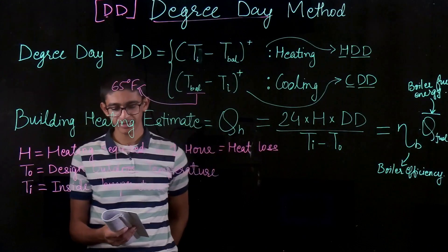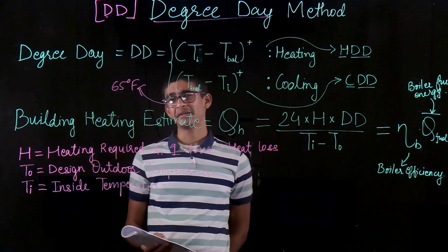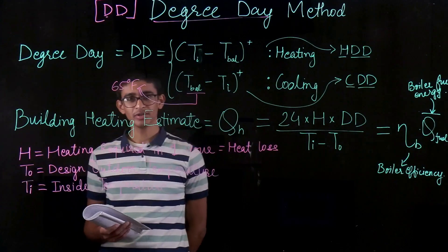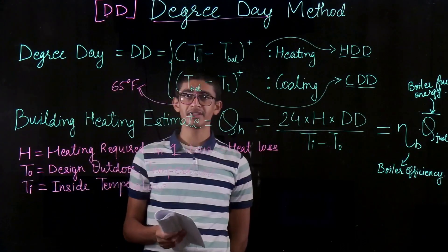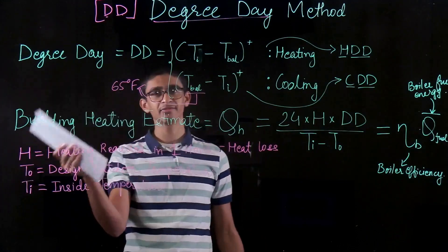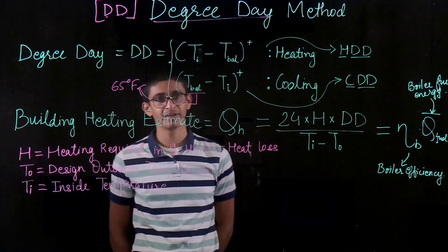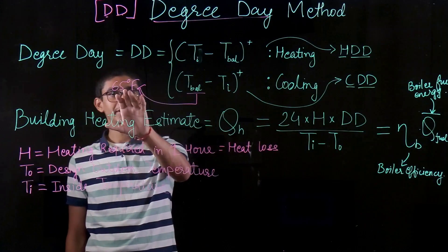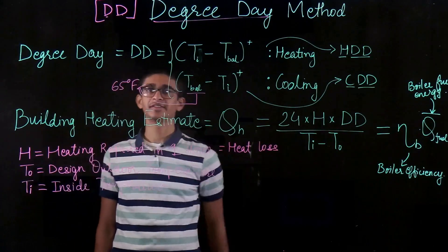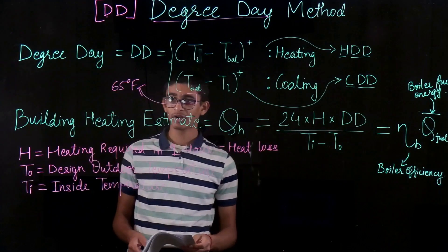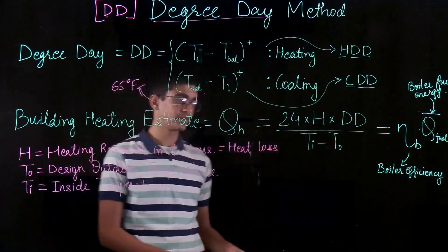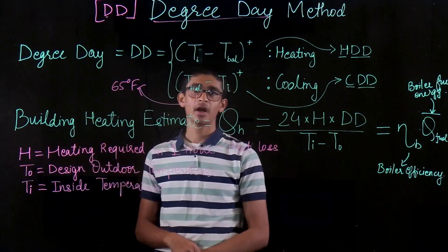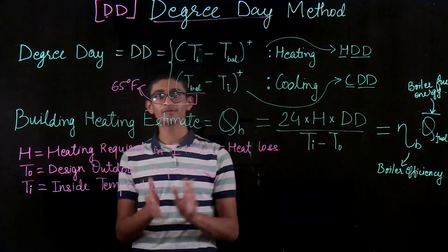The method very indirectly takes into account internal loads — because the comfort temperature inside a room is not really 65°F, it would be around 72 or 75°F. But to balance out those internal gains, we use 65°F as the balance point. Additionally, we are not zoning the building into multiple zones; this is a single-zone assumption, which is another disadvantage.